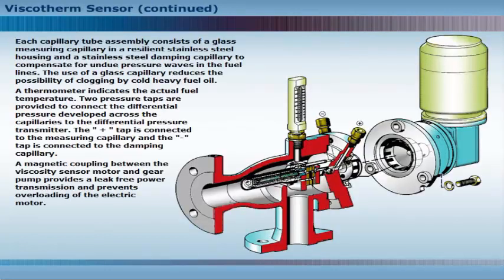Each capillary tube assembly consists of a glass measuring capillary in a resilient stainless steel housing and a stainless steel damping capillary to compensate for undue pressure waves in the fuel lines. The use of a glass capillary reduces the possibility of clogging by cold heavy fuel oil. A thermometer displays the actual fuel temperature. Two pressure taps are provided to connect the differential pressure developed across the capillaries to the differential pressure transmitter.